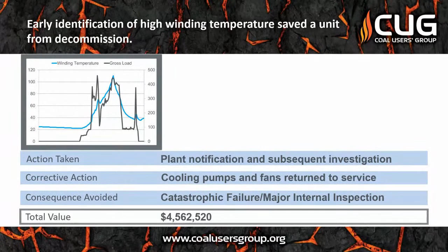It was actually left in the off position after work from the T&D group was completed during the outage. The operator returned the disconnect, obviously, to the on position. The cooling fans and the oil pumps were returned to service. And when he did rack everything back in conjunction with returning the power, the plant control room at that time did receive a high winding temperature alarm. The power for all the annunciators at that time was fed from the same source as the cooling fans and the oil pumps. So preventing this catastrophic failure of a transformer at the time was valued around $4.5 million. This specific unit that we have in the fleet has a low capacity factor. It doesn't run all that often. And it's likely that had we failed that transformer, the unit may have been retired. So this was a good catch.